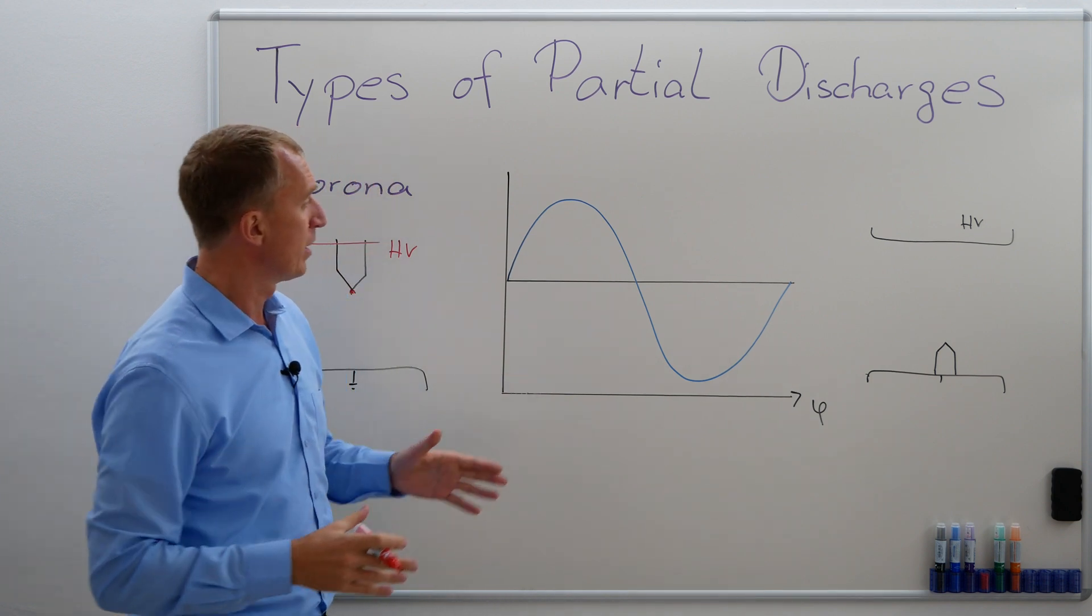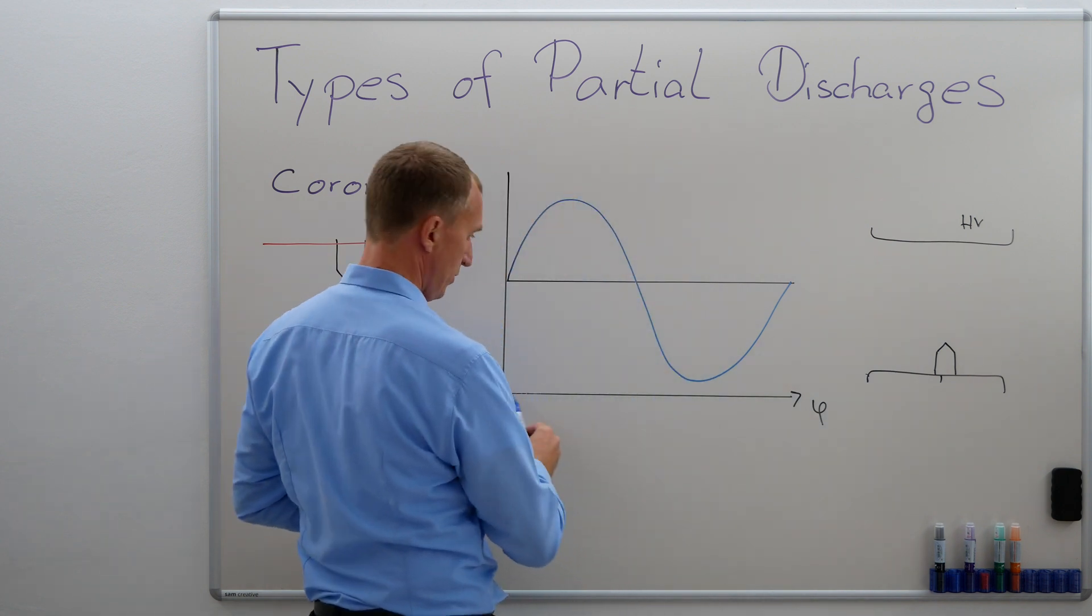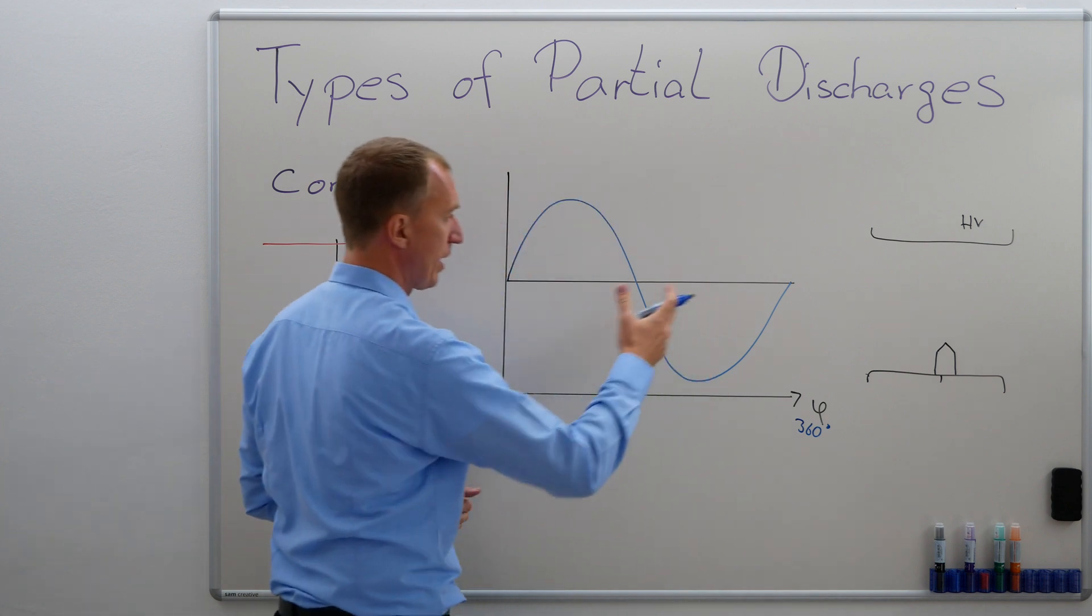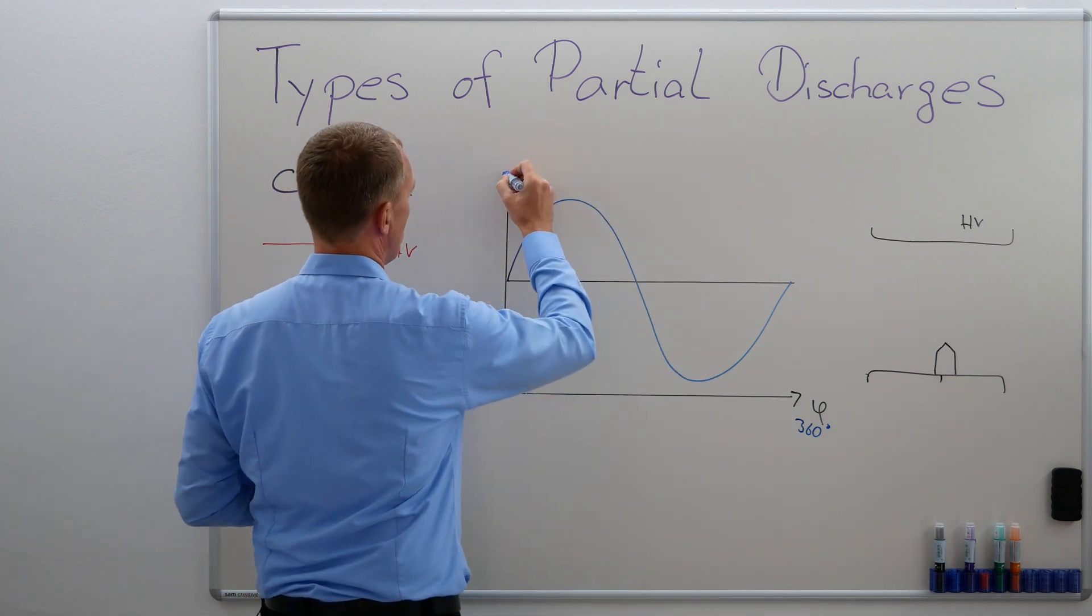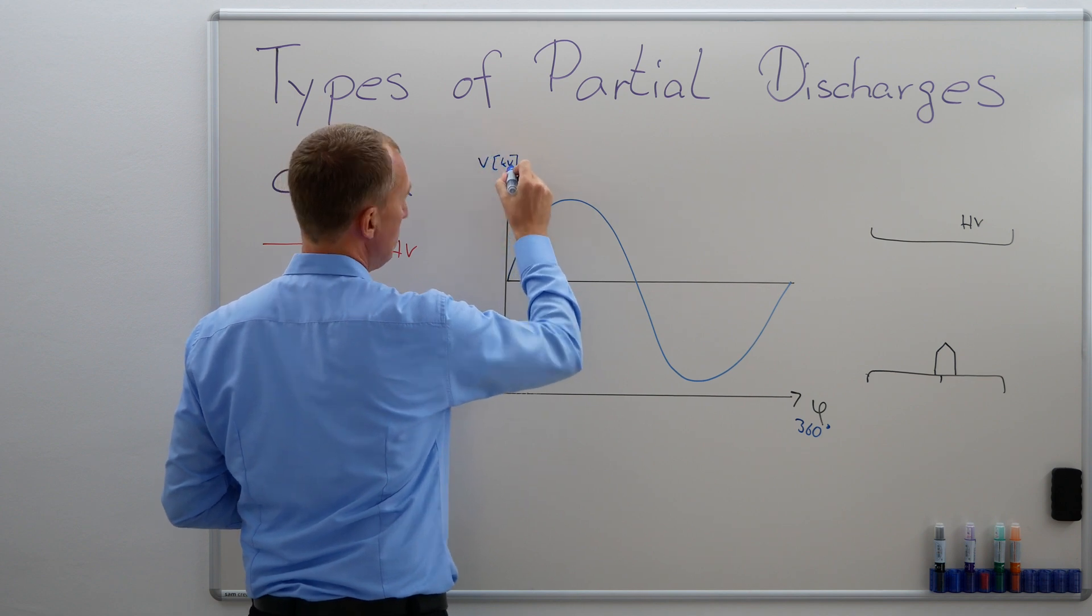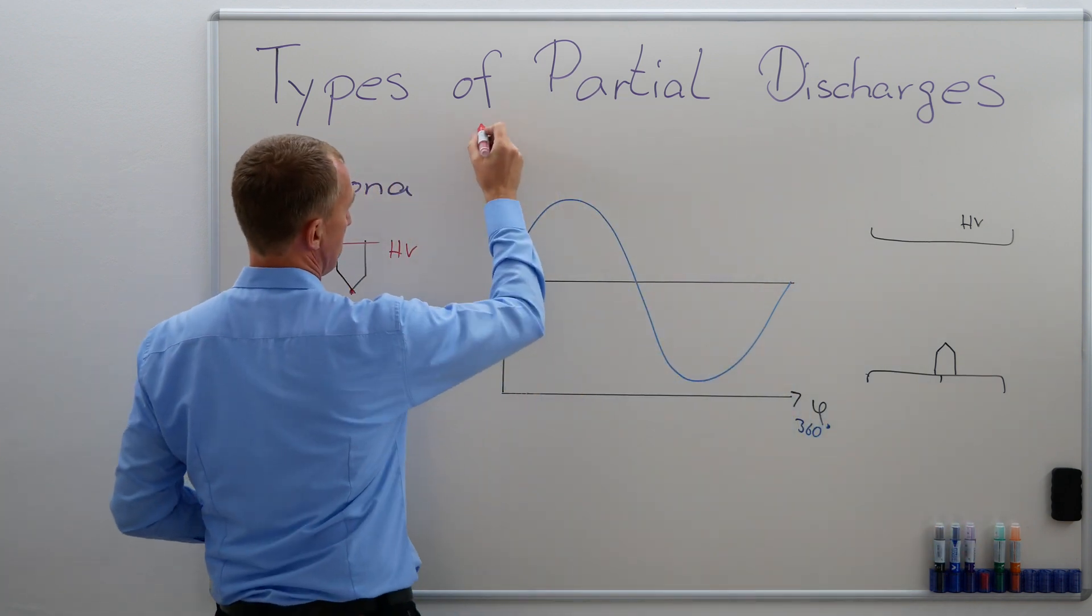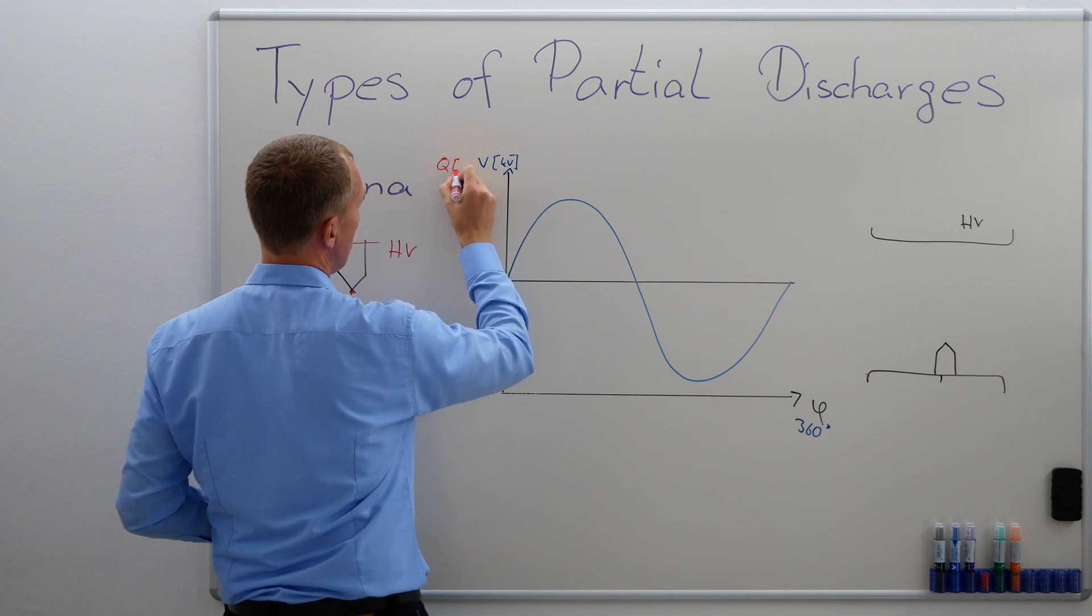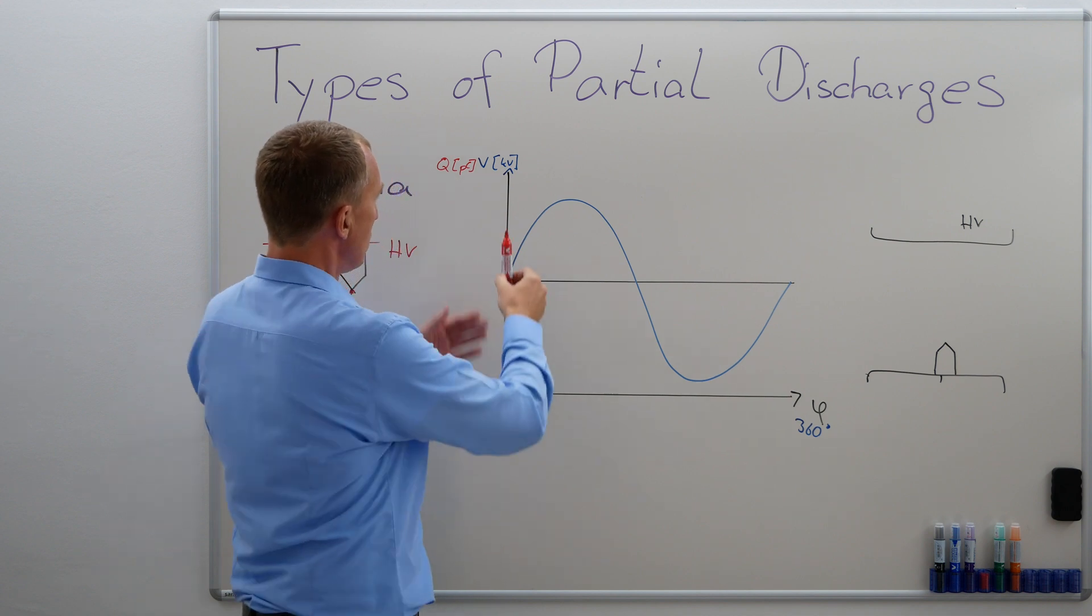Small ones but multiple ones. So if I'm looking at my PRPD diagram over here, so here I have my phi, so this would be 360 degrees of my AC voltage that I'm going to measure partial discharge in, right? So I could say this is voltage, let's say, in KV. And also, it's not only this, but in another scale, it is Q in picocoulomb. And I'm going to use red here for the time being.